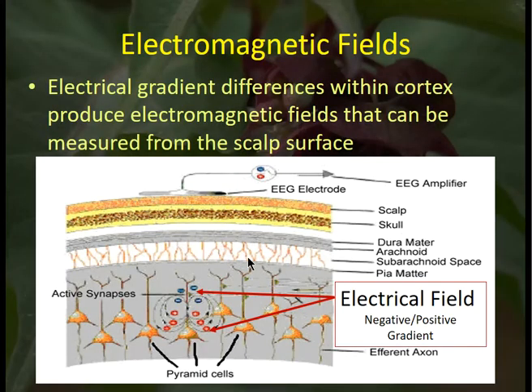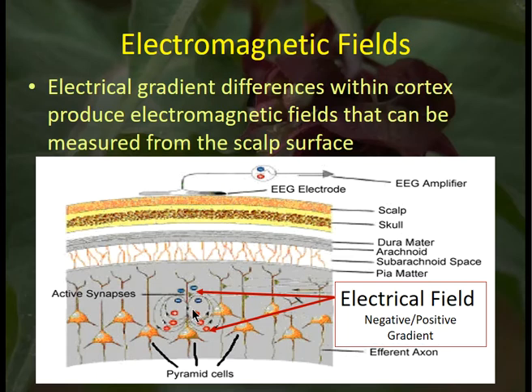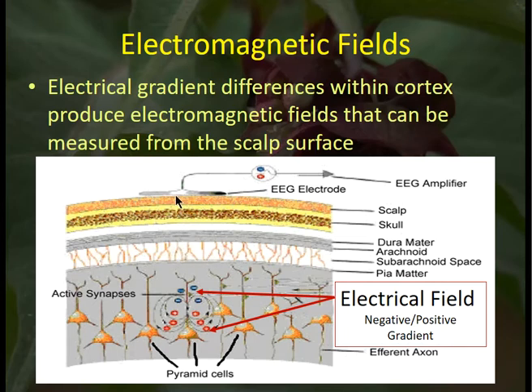We are measuring electromagnetic fields that occur in the cortex, but we're measuring them from the scalp surface. There is a positive-negative gradient within the cortex created by cellular mechanisms that transport mineral ions — containing positive and negative electrical charges — into and out of cells. This creates electromagnetic fields in the millivolt range in the cortex, subsequently attenuated by all the structures in between and reaching the scalp electrode as microvolt-level electrical readings, which are then sent to the EEG amplifier to be processed.